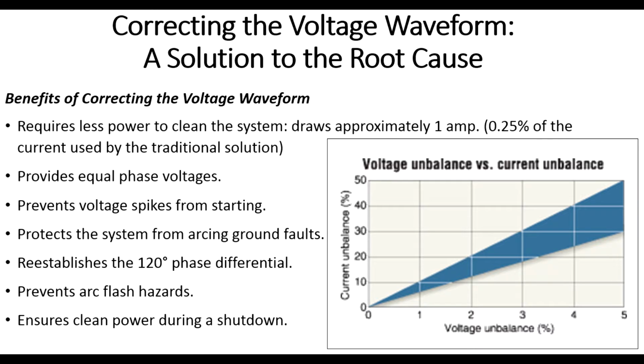Even facilities that have relatively clean power, when they switch off to generator and switch back to the grid, lose their voltage and frequency reference when disconnected from the power source. Mother Nature causes this to happen many, many times during a storm. The voltage and frequency do whatever they want as soon as the breaker opens. Spinning motors operate as generators and can typically cause the frequency to go extremely high for a second or two or five as motors are spinning down. This can cause a lot of failures of power supplies, and confused controls that will lock up and just not come back up when you reestablish power.